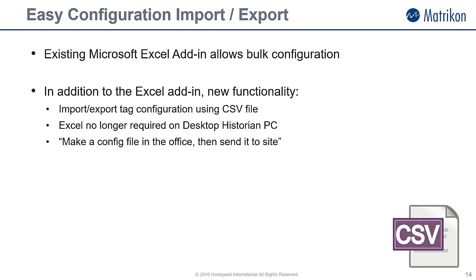Previously, Matrikon gave you a Microsoft add-in menu item that allowed Desktop Historian to be configured in Microsoft Excel. Although a great feature that is still present in version 5.1, the downside was that you needed Excel installed on the Desktop Historian PC to utilize this. There is now, in addition to the existing functionality, a CSV import-export facility. This allows you to bulk input tags to be archived into Desktop Historian using a simple comma-separated value file. You can now create the configuration ahead of time and ship it to site with the installer.